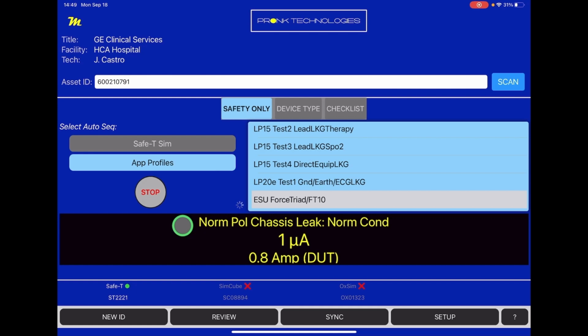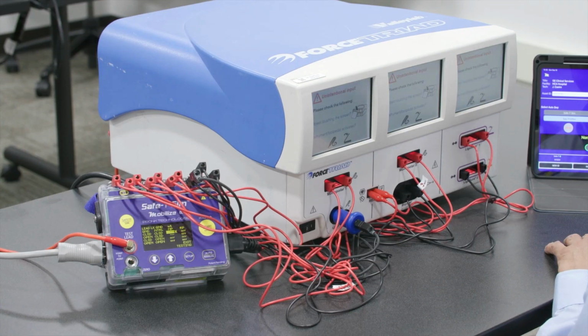So in this lower window here, you'll see the name of the test. We're doing a normal polarity chassis leakage test in normal conditions. Below that is the measured leakage that we're measuring. And then below that is how much current the device under test is drawing. So you can see as it's booting up, the current draw is ramping up as well. So it's going to go ahead and do all of those tests as we're running through it.